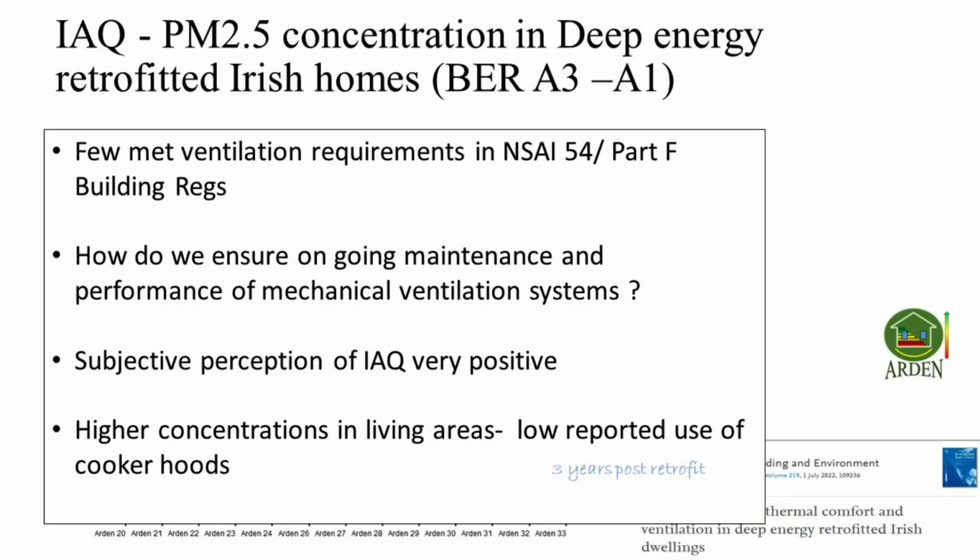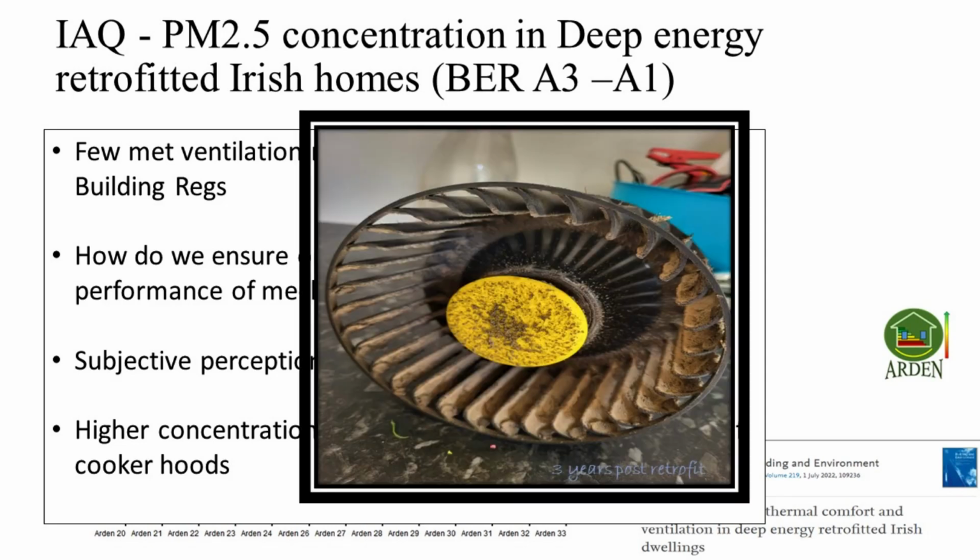Now, a lot of the systems that were installed are capable, I'd say, of complying. But the issue seems to be really around maintenance. And following on from the study, we have had lots of conversations with homeowners and also the retrofit providers. This is just a picture that was provided to me a few weeks ago from one of the homes that went back to the retrofit provider because they weren't happy with the results that they got in the surveys, and the engineer went out to have a look at the ventilation system. This home is only 3 years post retrofit.